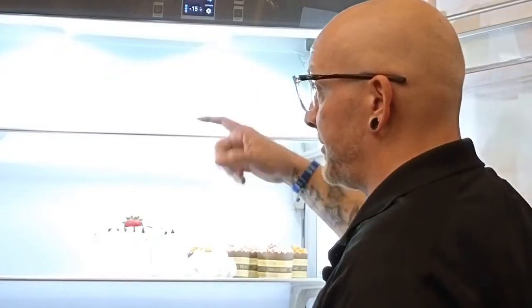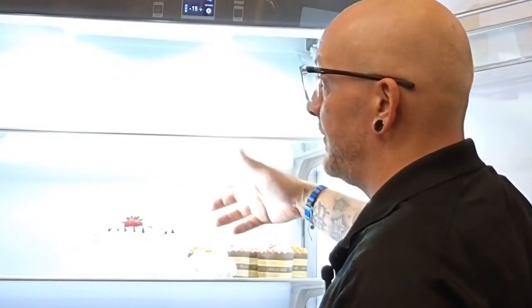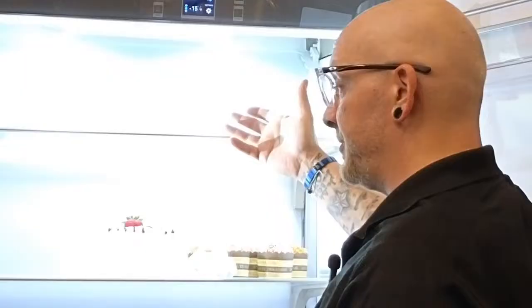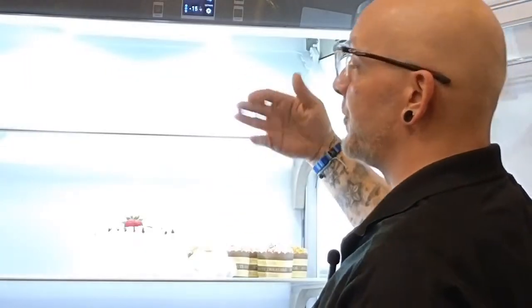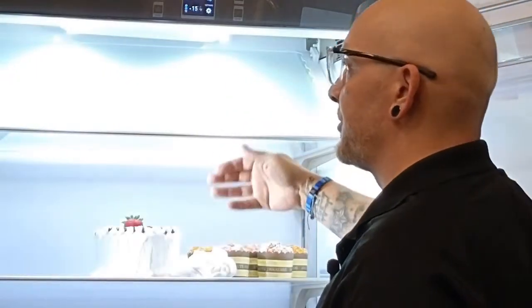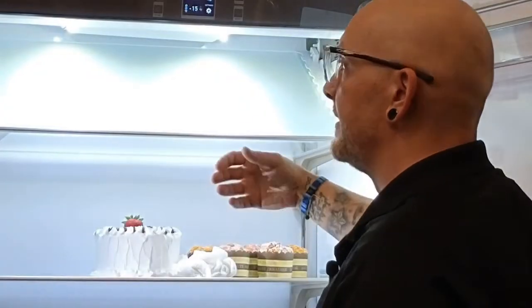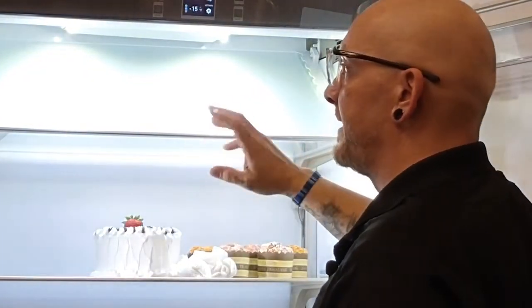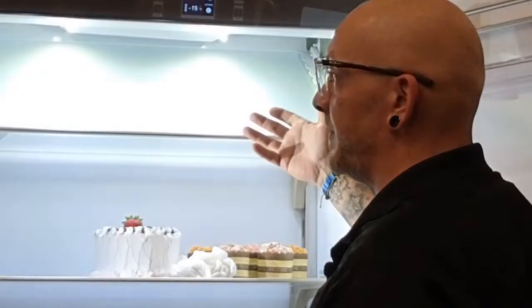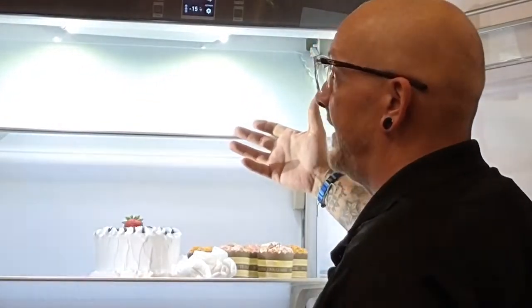Or whenever you replace your water filter. That's another big one. Whenever you replace the filter, if the customer is using the filter, you want it to pull some water through that filter to remove all the charcoal, and make sure that you've got clear ice. So you're going to want to run that manual clean anytime you change that filter. Again, that filter reminder is once a year, 365 days.